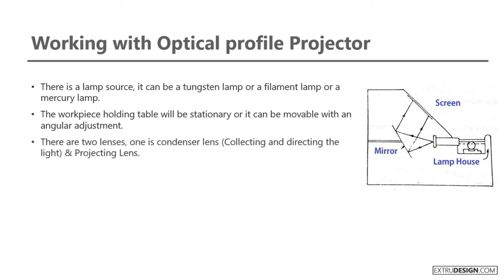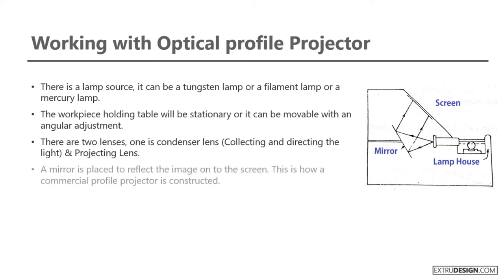There are two lenses, one is condenser lens which is collecting and directing the light and the second one is projecting lens. A mirror is placed to reflect the image onto the screen. This is how a commercial profile projector is constructed.